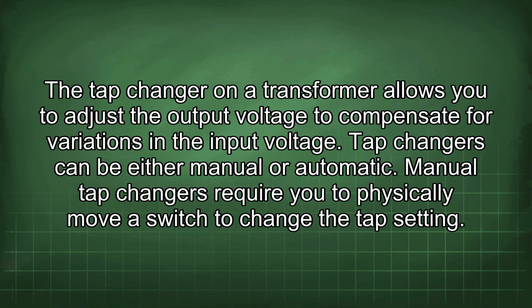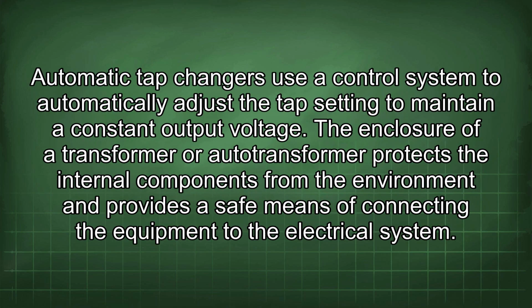The tap changer on a transformer allows you to adjust the output voltage to compensate for variations in the input voltage. Tap changers can be either manual or automatic. Manual tap changers require you to physically move a switch to change the tap setting. Automatic tap changers use a control system to automatically adjust the tap setting to maintain a constant output voltage.